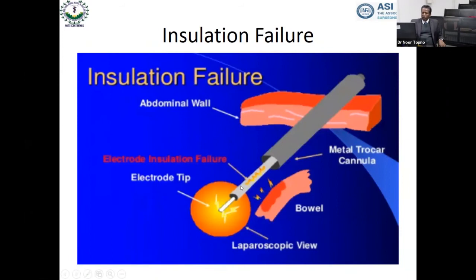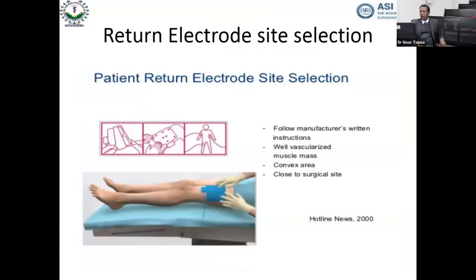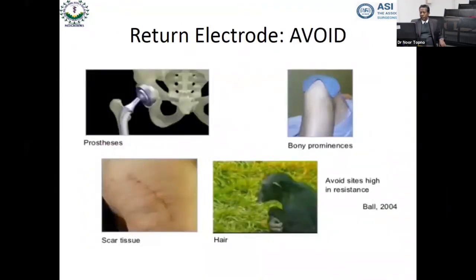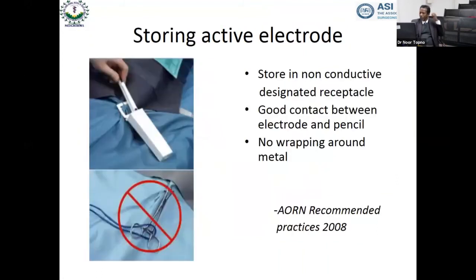Insulation failure. Now, in insulation failure, the key thing is if there's a small crack or defect in the insulation, then as compared to an area with a large defect, in a small defect the density of current that is collecting is much, much higher, and therefore the damage is much greater. Return electrode selection, these are some of the areas where you have to ensure that if you put it on a well-vascularized area, it works well, whereas on a less vascularized area, you have problems. Storing, you need to store it probably in something where the conduction is much less, and do not do this.